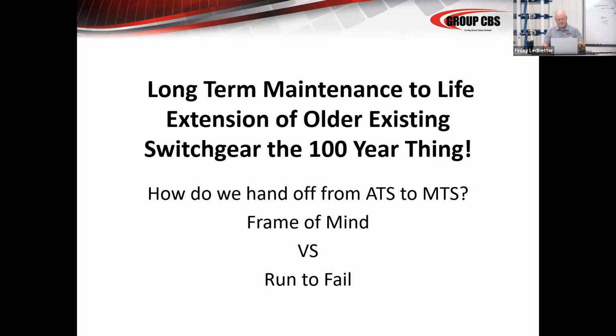We'll get into it in maintenance where you might expect to see some of that. But I always ran a magnet in the bottom of every cell. If it picked up any filings, I would bring that to the attention of the owner, because you should not have metal filings being cut by the breaker or the racking mechanism day one. If you do, it's going to develop long-term problems.